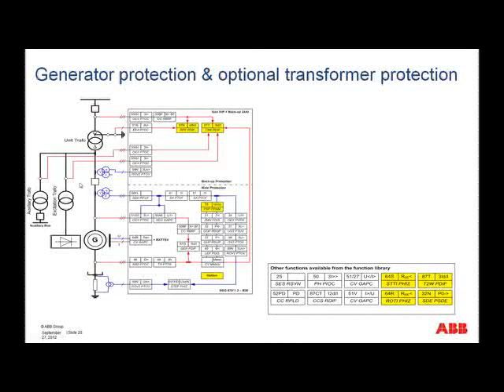Then if we have a look here, you'll see we have these auxiliary transformer or excitation transformer. Now, of course, these would have their own protection, but in this case, instead of including a second function or a second box for each one of those to act as backup in case the primary protection failed, it is actually possible to include those functions here. So taking this auxiliary transformer as an example, it would have, as I said, its protection, but instead of including the second function, box here, to cater for the possible failure of that first box, this can be put back into this IED here.